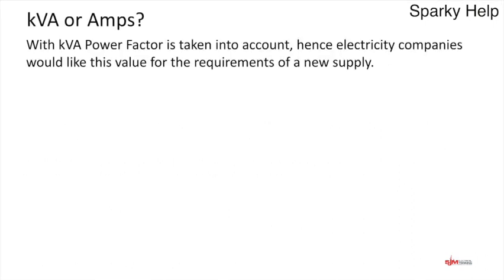So the question is: do we put KVA or amps? KVA — K meaning thousands — is volt-amps, literally volts times amps, but it's not power because otherwise it would be watts. KVA has power factor taken into consideration, so you're not ignoring the power factor. KVA is the preferred value of demand by electricity companies; expressing demand in watts doesn't really tell them much, because a poor power factor would make the KVA much higher. Hence we can express maximum demand on the certificate as KVA.